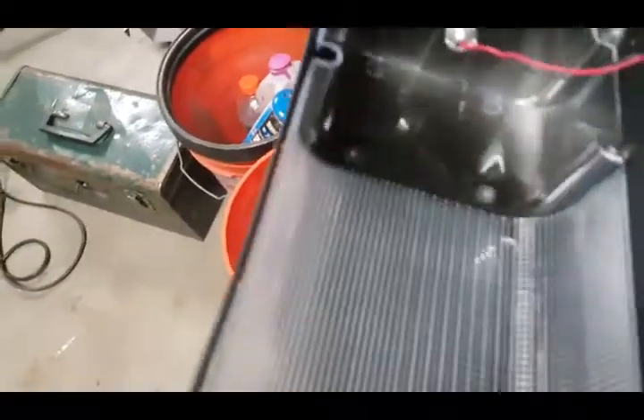There's our polycarbonate lens. We're talking about a 1/8 inch thickness, so if you hit this thing with something, it will definitely shatter. It is not shatterproof. Polycarbonate is resistant, but this is a very thin polycarbonate. And it's textured so that they can disperse the light as much as possible. And right here we have a photo, that's our photo cell right there, wired right into the transformer here.